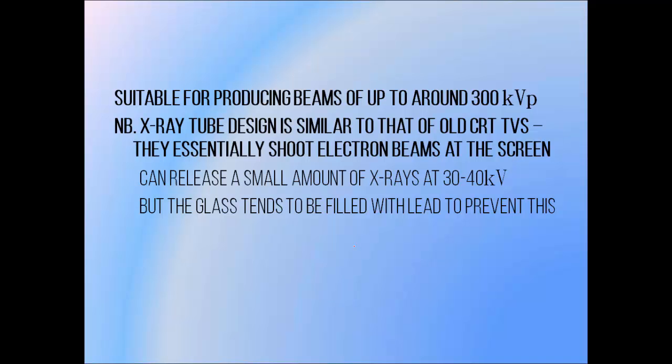X-ray tubes are relatively low energy. Practically speaking, they're good for producing x-ray beam energies up to about 300 kVp. They can go higher, but it's no longer practical given the other equipment we have available for high energy therapy.